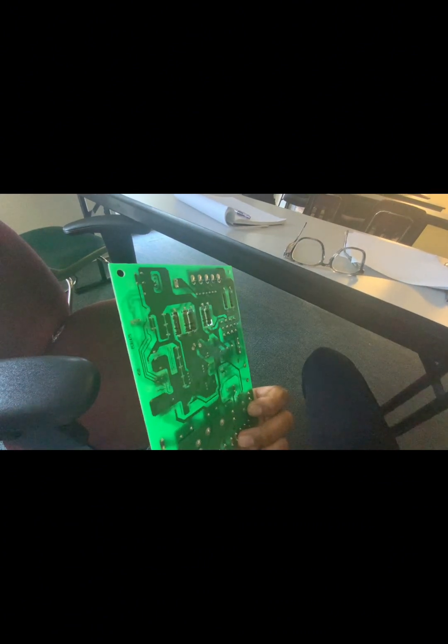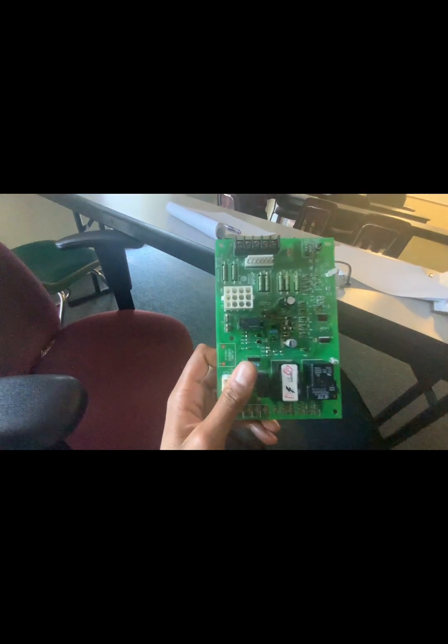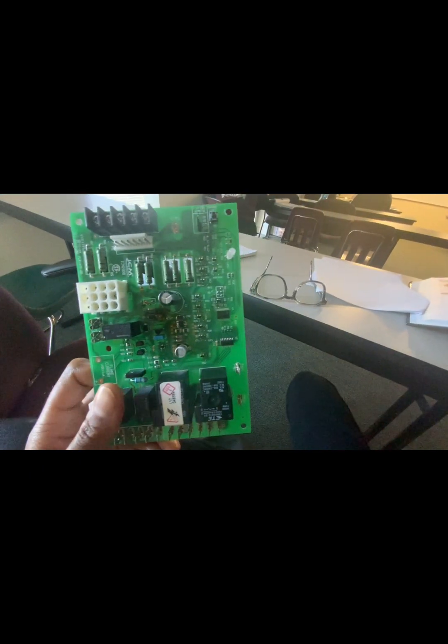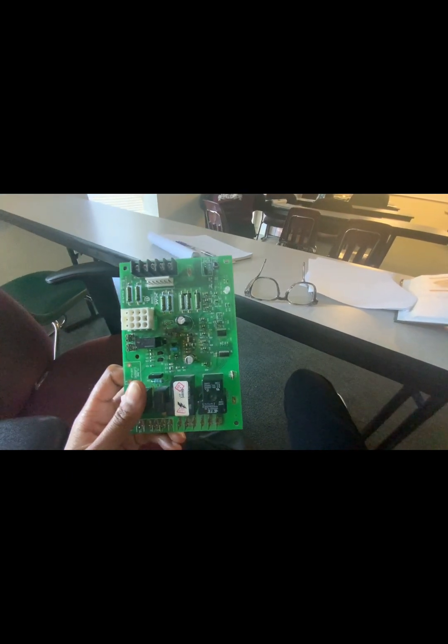And the biggest thing is what terminal is the coil on? You got 1, 3, 5, 2, and 4, or 2 and 5. What terminal is the coil on? There's 2 sets of contactors. That's not a potential. That's just a normal relay with several contactors, normally open and normally closed.